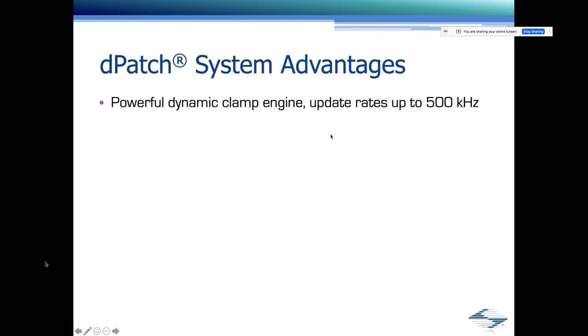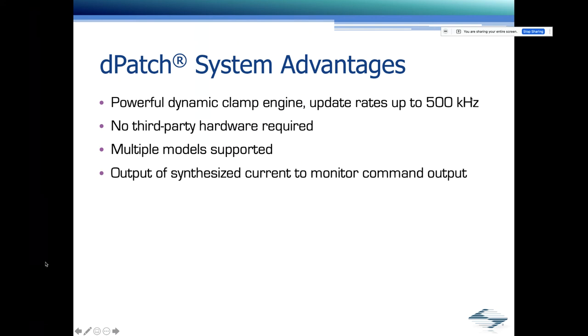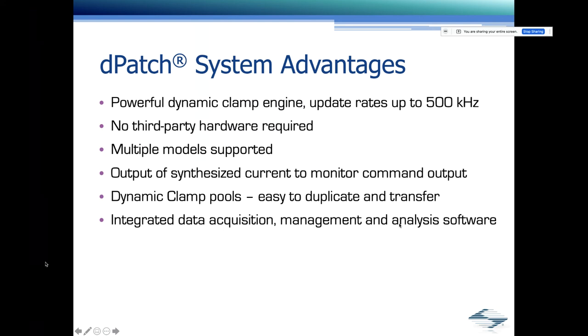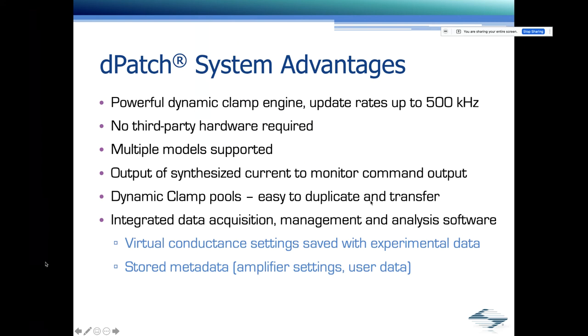So what we have here is our inactivating step. And then at the end of the step, the intervals between the step and our test pulse increase. And here again, I show in real-time the recovery. Let me briefly summarize the advantages of the DPATCH system. We have a powerful dynamic clamp engine with update rates of up to 500 kHz. You do not require any third-party hardware for that. That is a big advantage over other systems available. We have multiple conductance models that are supported. The synthesized current can be monitored, as I just showed you. And that can also be used for assay development. And we have dynamic clamp pools. The data acquisition management and analysis software is integrated and included with the DPATCH. The conductance settings are saved with the experimental data. Metadata. And there's powerful analysis tools available. And with that, let's switch to the question and answer session.